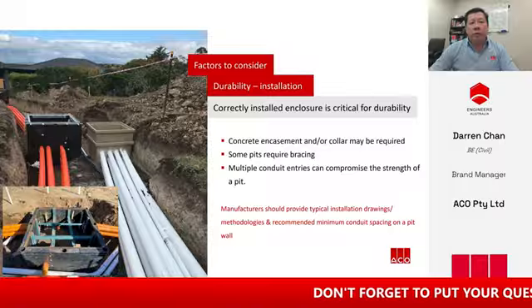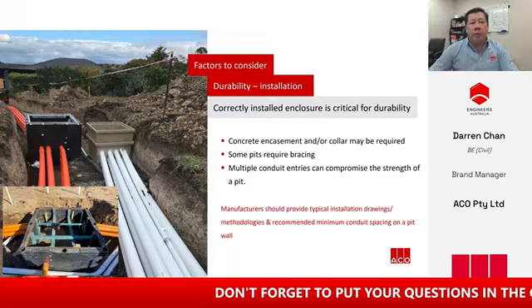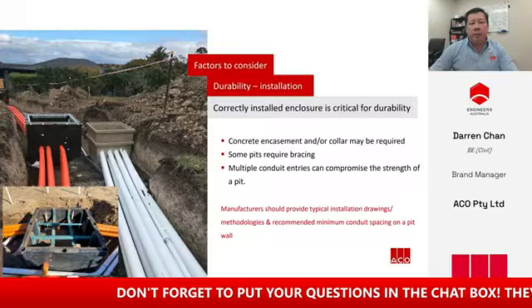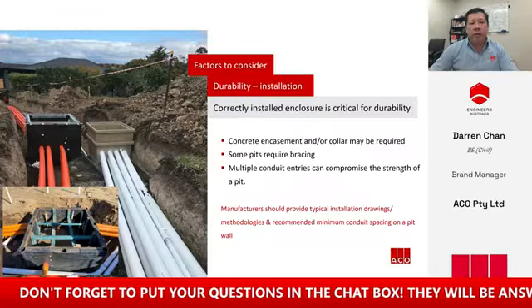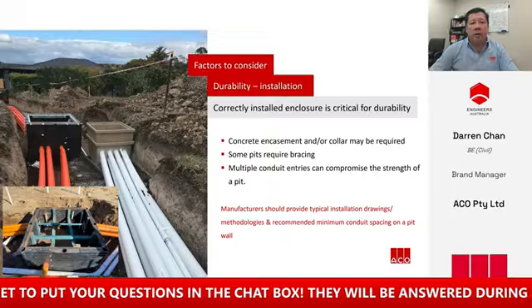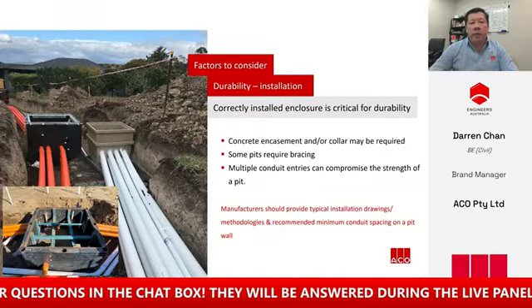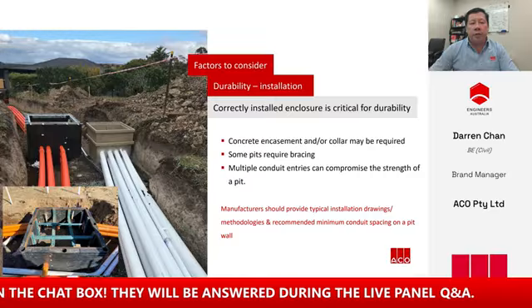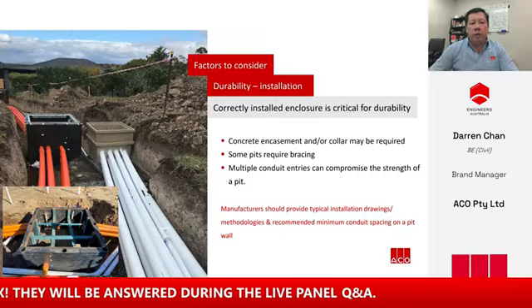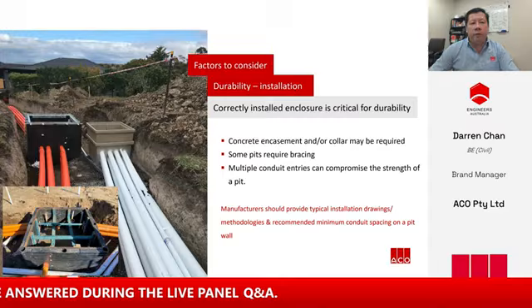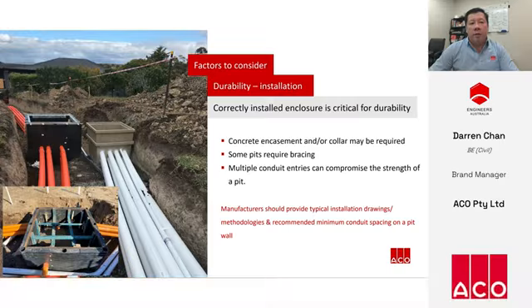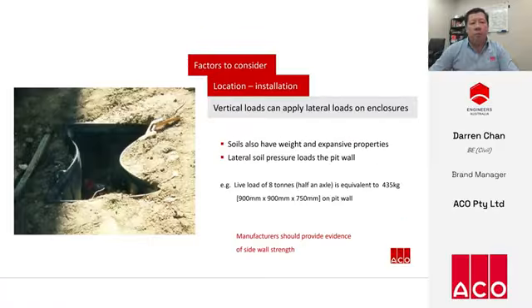A correctly installed enclosure is critical for long-term performance. Depending on the application and the pit material, a cement concrete encasement and/or trafficable concrete collar may be required. Some pits require bracing prior to compaction. Multiple conduit entries can compromise the strength of a pit, so this must be compensated for. Manufacturers should provide typical installation drawings and installation methodologies as well as recommended minimum conduit spacing on a pit wall.